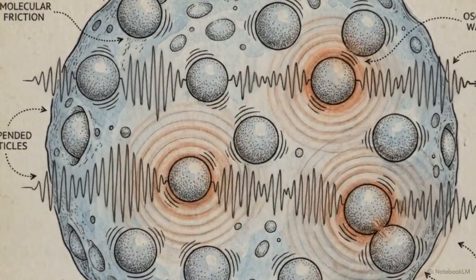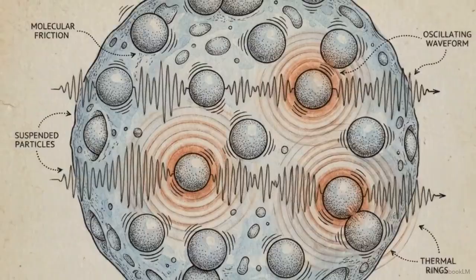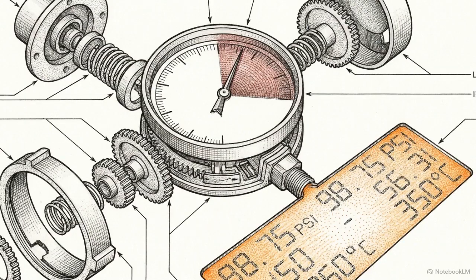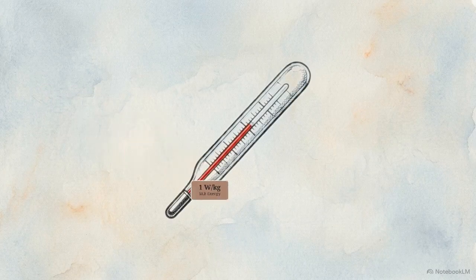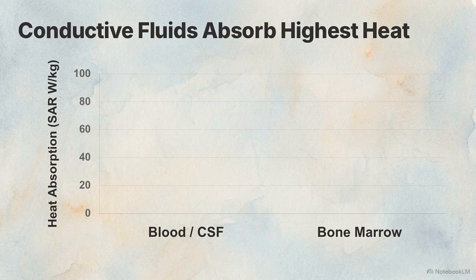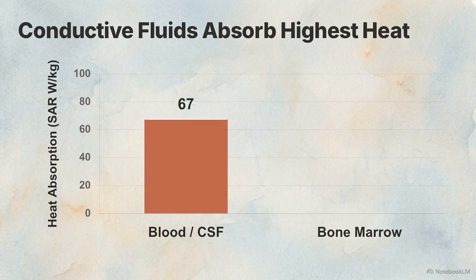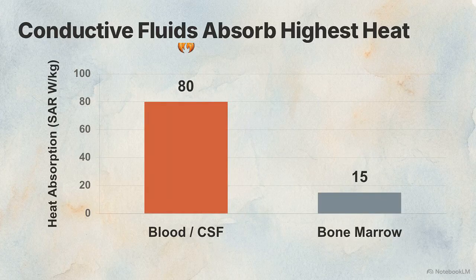These currents generate friction at the molecular level, which is then released as heat. This energy deposition is measured by the specific absorption rate, or SAR, in watts per kilogram. A SAR of 1 watt per kilogram results in a whole body temperature rise of 0.5 degrees Celsius. The risk of overheating increases in patients with impaired thermoregulation, such as those with heart failure, fever, or those taking vasodilators and diuretics. Tissue conductivity also dictates how much heat is absorbed. Highly conductive fluids like blood and CSF absorb energy more readily than low-conductivity bone marrow.